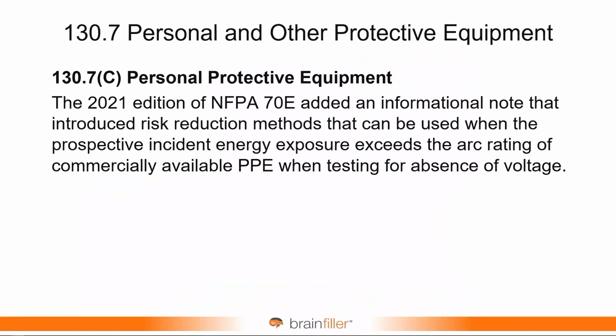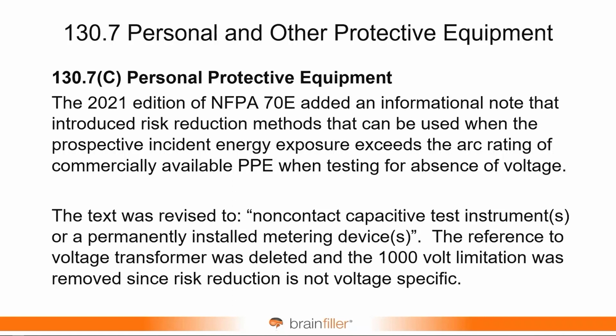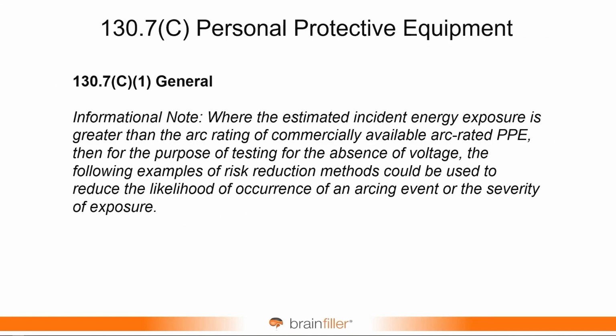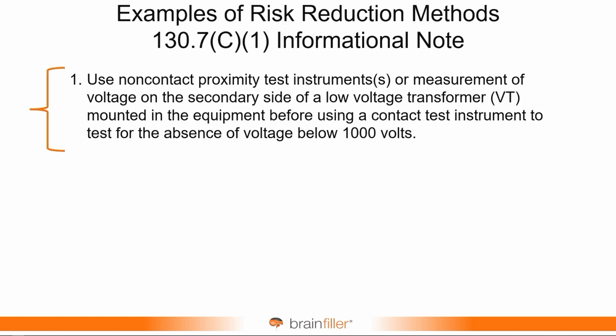So there was language introduced in the 2021 edition of NFPA 70E that provides risk reduction methods that can be used when commercially available PPE doesn't have a sufficient rating when you're testing absence of voltage. There was a modification made to this language. This is the note providing examples of risk reduction methods. And the first method, this is the one that was modified for 2024.